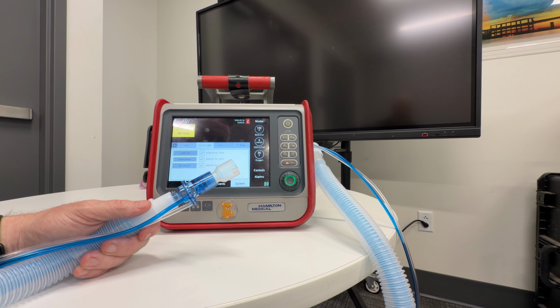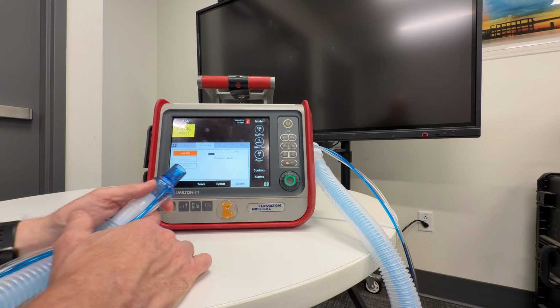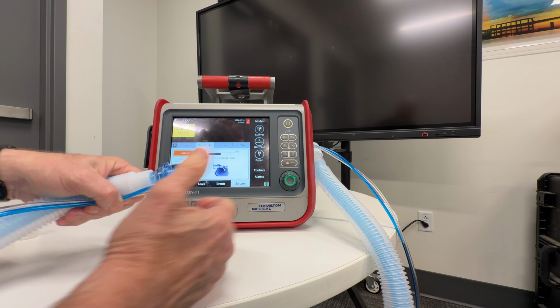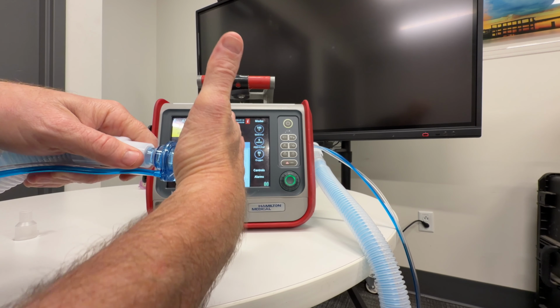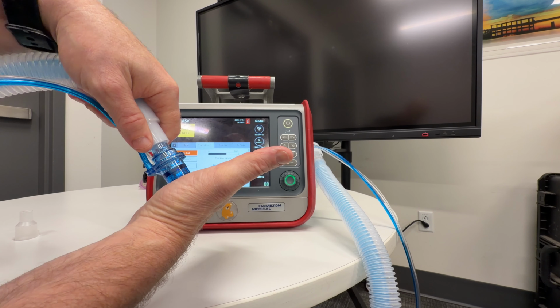Now we're going to move on to the leak test. So if you have to do a leak test, this is how you would do it. You would take this off, put it in your pocket, save it for later. We'll go to leak test. This is very simple. Same circuit, leaving it connected. It says disconnect from the patient. It's disconnected. Now it wants you to block it. So you're going to take your hand, seal it off just like that, and it's going to go through a series of tests. Just follow the directions and you'll be just fine. All right, it says reconnect. So you just unocclude it, and it passed.